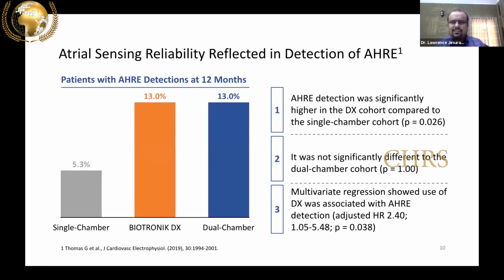When you look at these VDX leads, which have a channel in the single lead system, which have a channel in the atrial level, they have a very good accuracy in detecting the atrial high rate events compared to your dual chamber devices. It closely matches the accuracy of a dual chamber device. You have a single lead which can do the job of atrial detection.